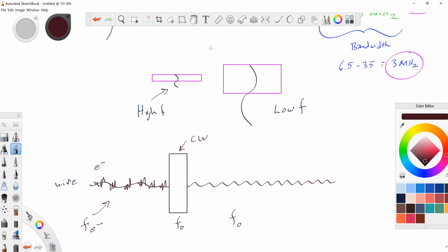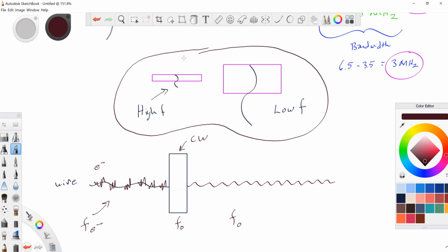On our pulsed transducers, it has everything to do with the width of the transducer itself. So there you go, Kurt. Don't read the question, get it wrong. What helps determine the frequency of the sound produced? Yeah, okay.